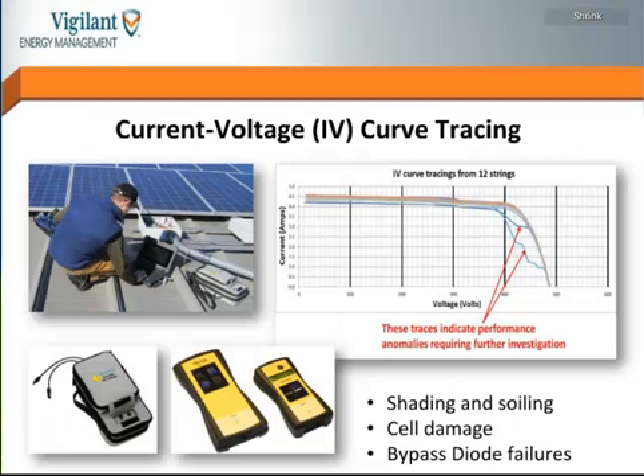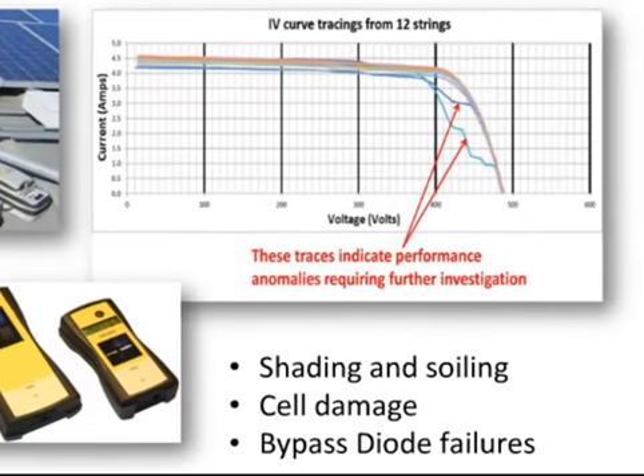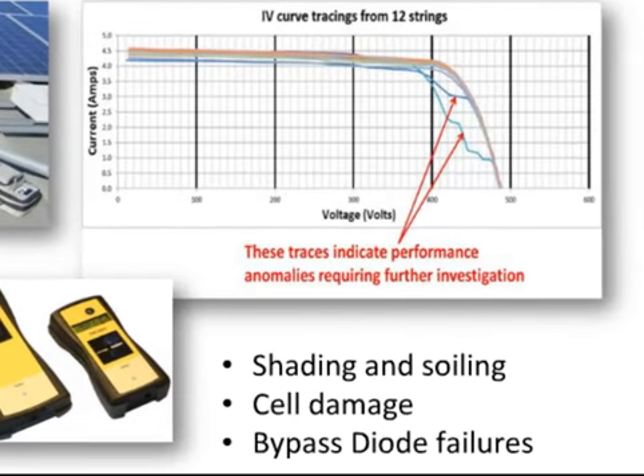Next I want to spend a couple words on IV curve tracing. IV stands for current voltage—the I is actually for current intensity. With these devices we get a graphical representation of the performance of each string of modules in an array. So we may have, say, 14 or 20 or so modules in a series string, and that string is tested.